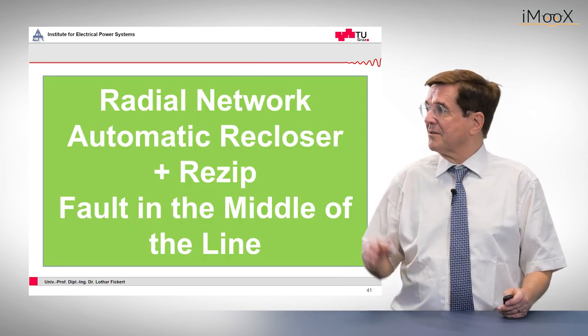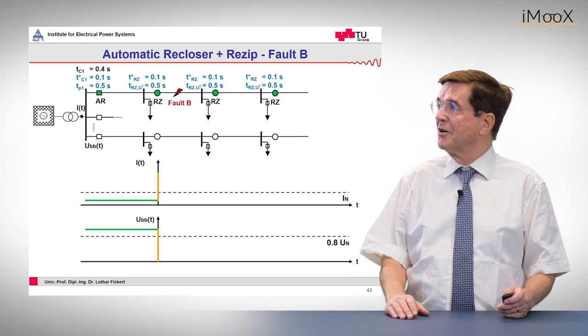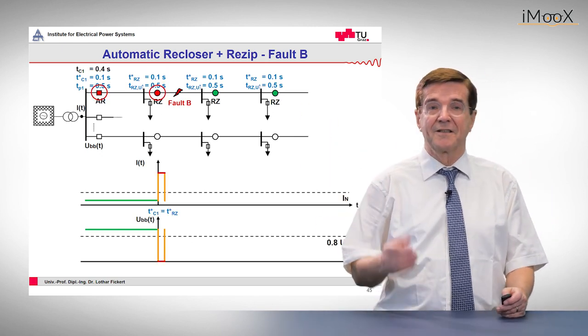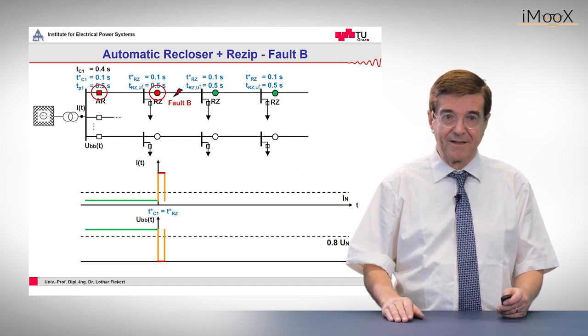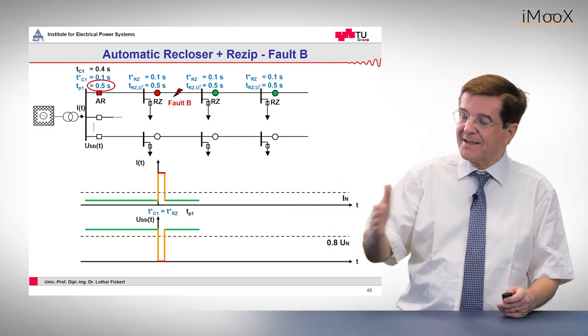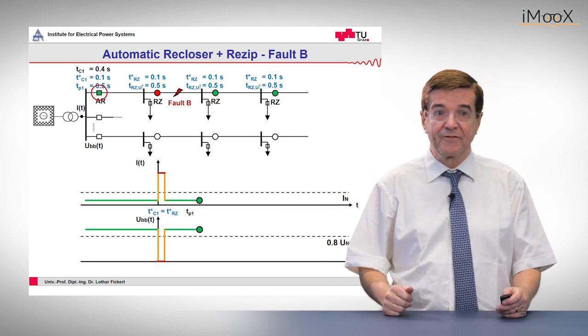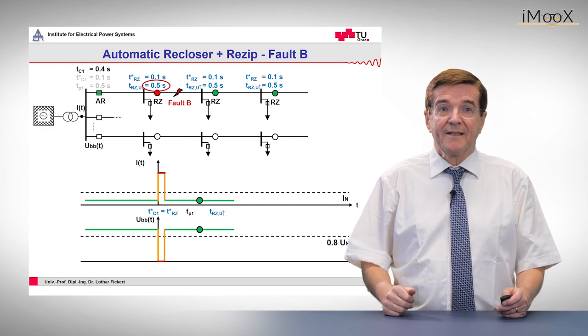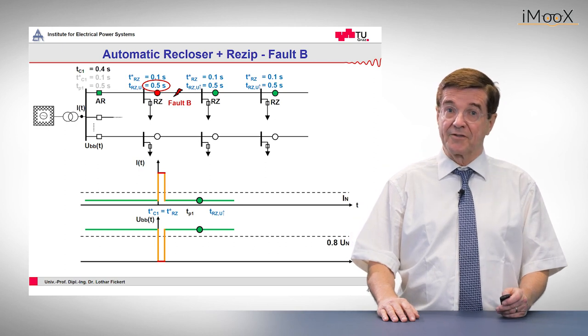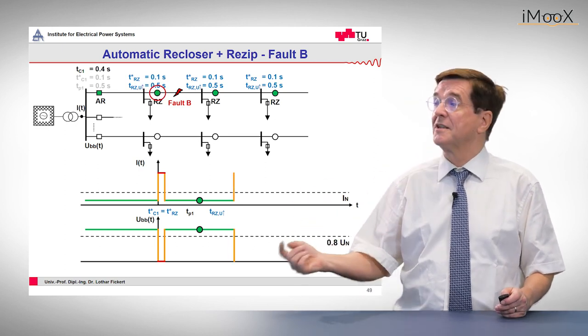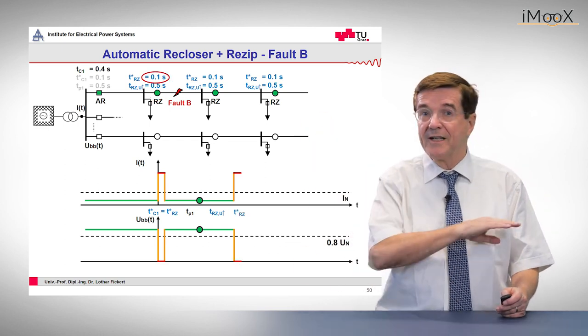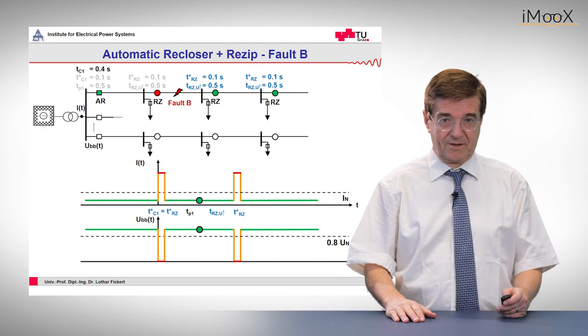Now we can see the same, to repeat it again, for a fault in the middle of the line. The fault occurs and all afflicted auto reclosers trip immediately. And now after a time of 0.5 seconds, the recloser and the passing on of the voltage starts again from the left side. The next re-zip auto recloser sees the incoming voltage. After half a second it closes, but unfortunately it closes on fault. Again the current goes up, the voltage goes down, you trip out immediately, and that was it.